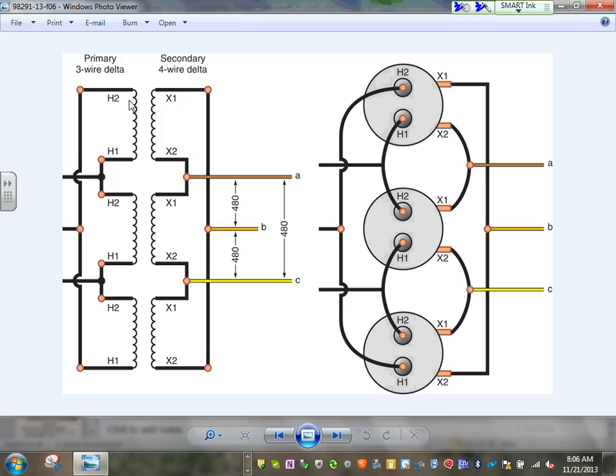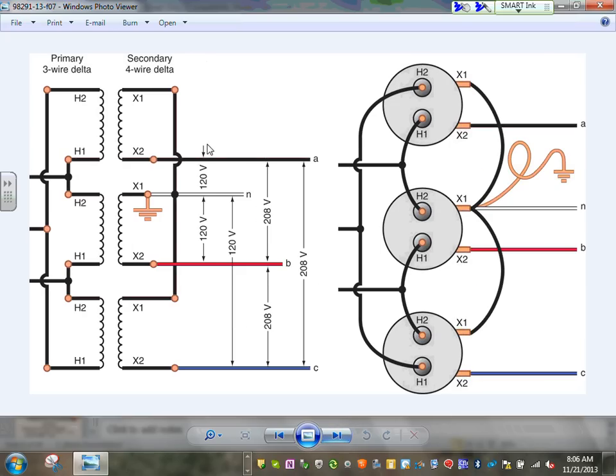The high voltage terminals are always labeled H. The low voltage terminals are always labeled X by the manufacturer. That's it. High voltage H, low voltage X. No question asked, that's how they label them. Let's get you 480 or 600 volts. The most common ones, guys, are this type of connection, where you take the primary delta and the secondary Y.